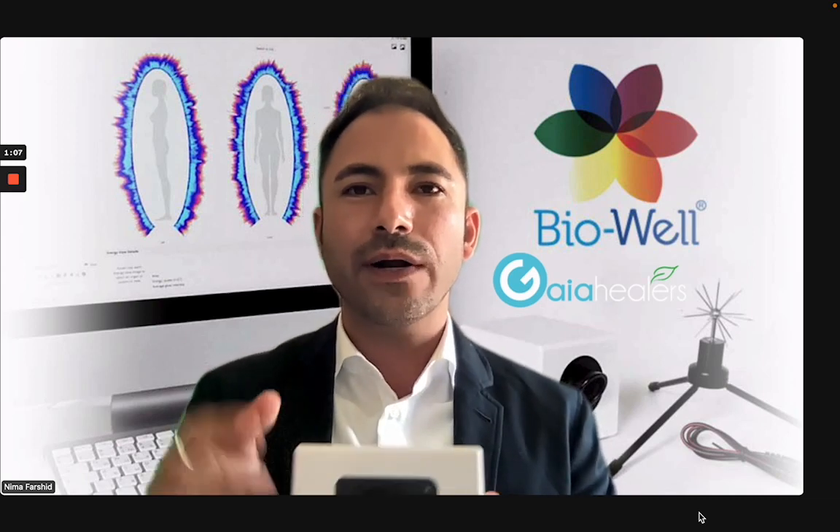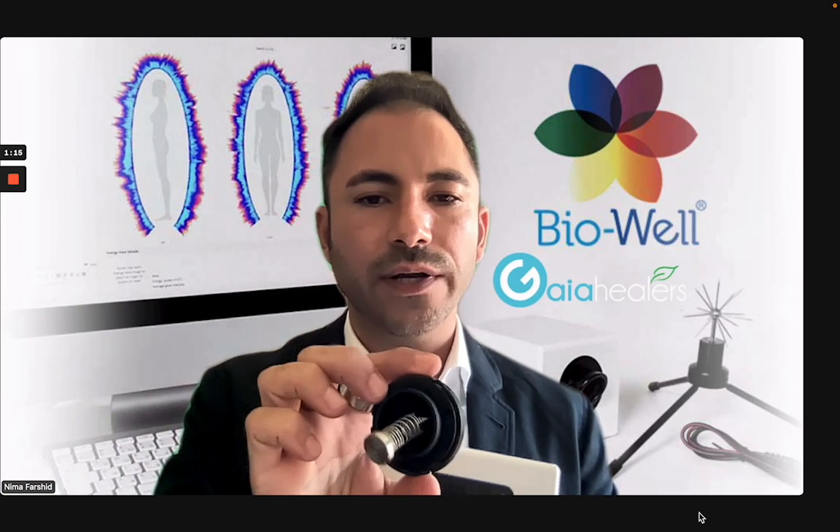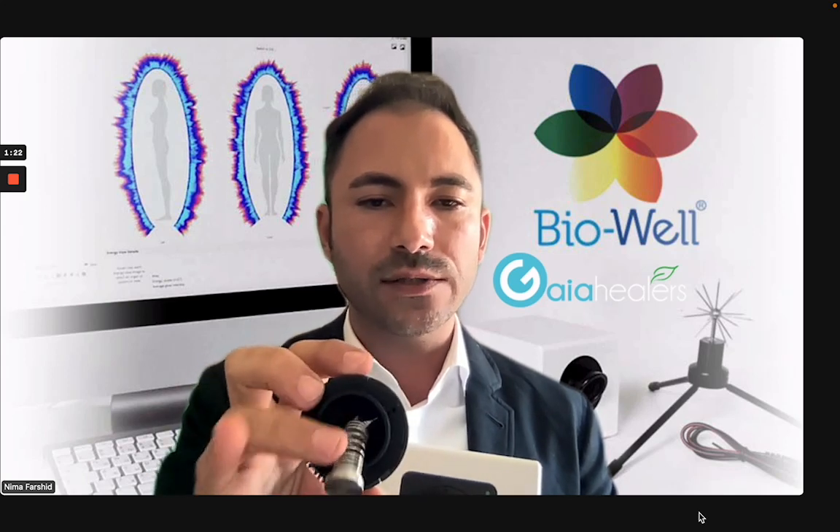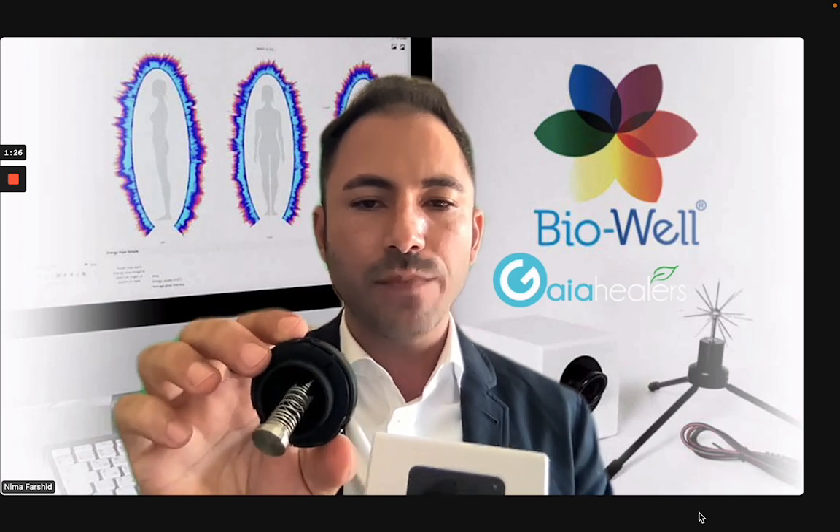On the 3.0 we don't have a calibration wire — the calibration wire has been built into the technology. The only thing you have for calibration is this little device right here. One thing to pay attention to before you do your calibration: make sure that the spring hasn't been pushed in — make sure it's nicely extended. You can gently grab it with your fingers and pull just a little bit to make sure that when you're placing this inside of your camera, the flat tip of the cylinder sits flat on the screen inside of the Bio-Well device.